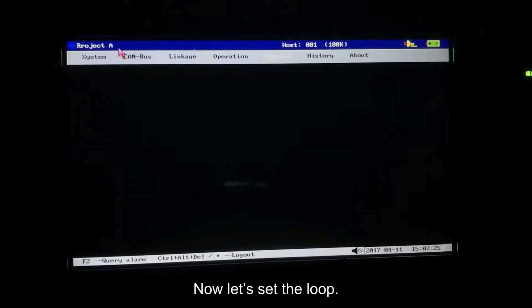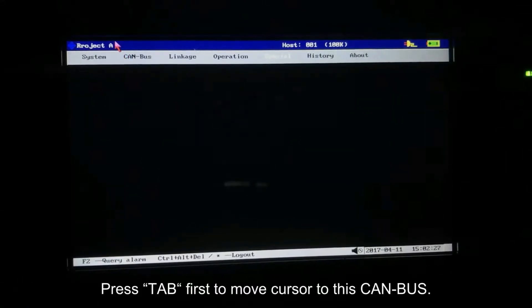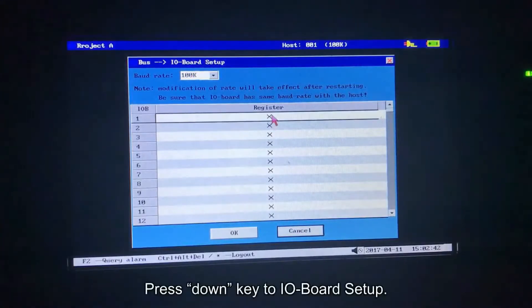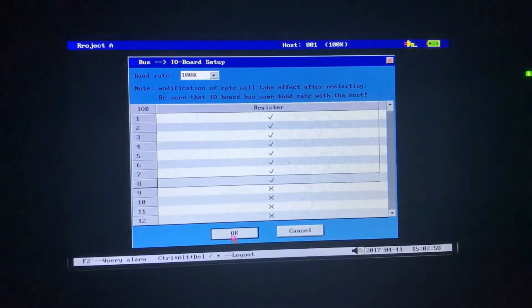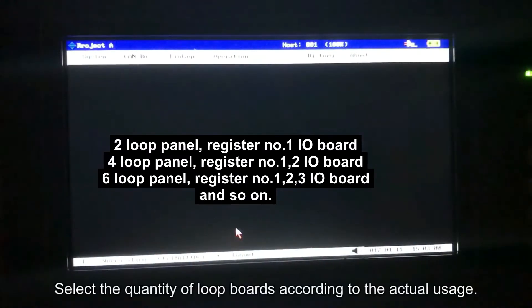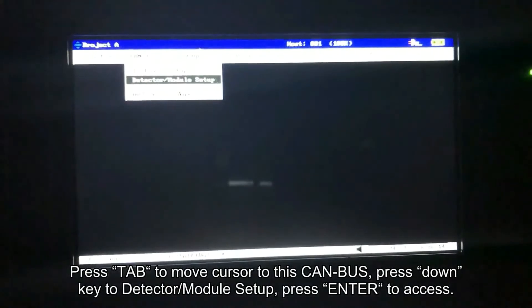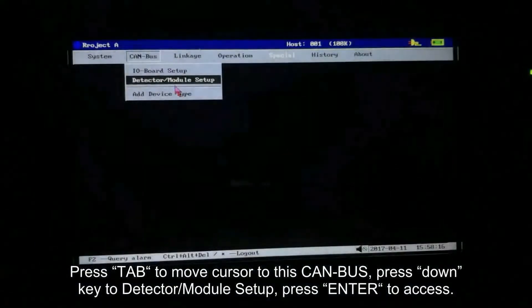Now let's set a loop. Press tab first to move cursor to this CAN-Bus. Press down key to IO Board Setup. Press enter to access. Select the quantity of loop boards according to the actual usage. Press tab to move cursor to this CAN-Bus, press down key to detector and module setup. Press enter to access.